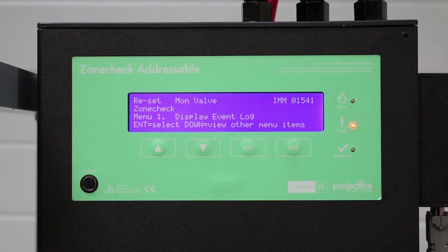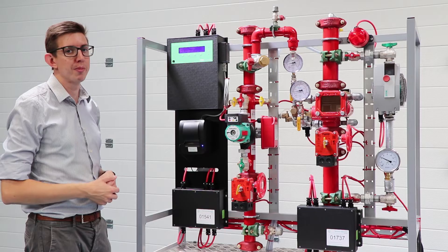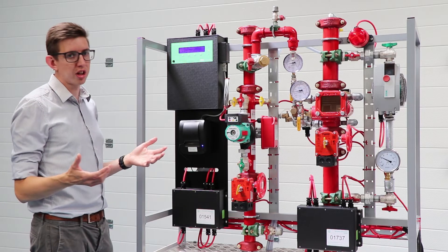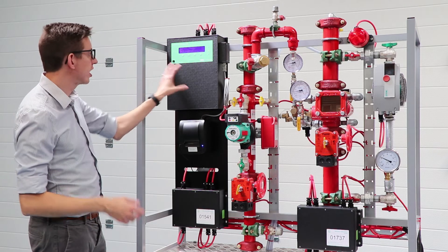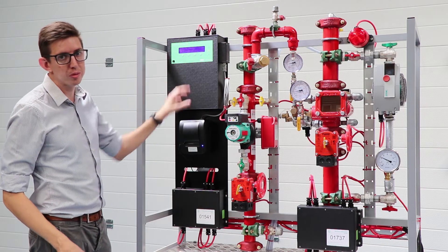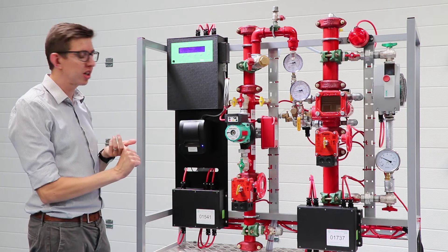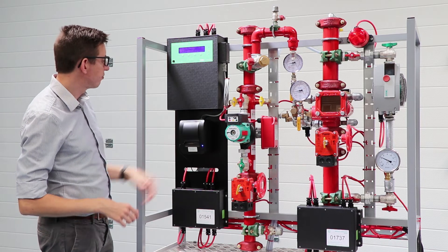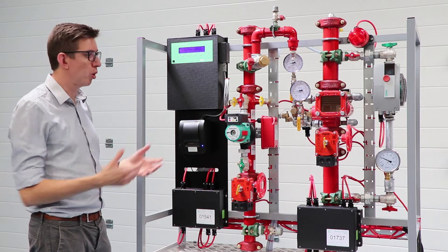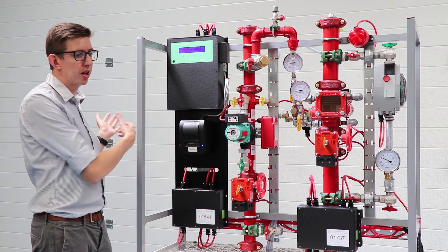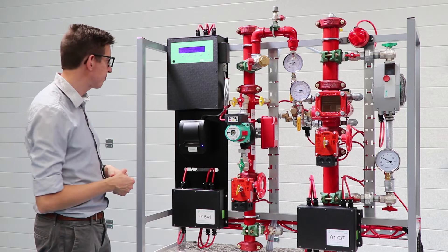So it's giving you location information and detailed information about your system. If anyone wants to close the valve for any reason, you're going to know about it, and you're going to have a date and timestamp log that can sit on an SD card within the controller. That can be downloaded to a PC or sent via a BMS connection to a SCADA system.